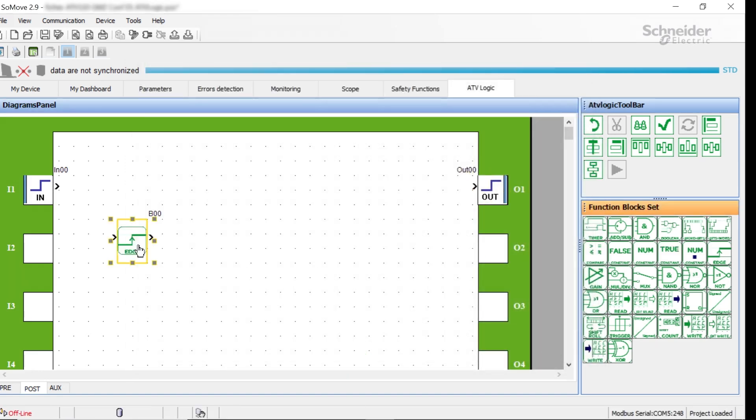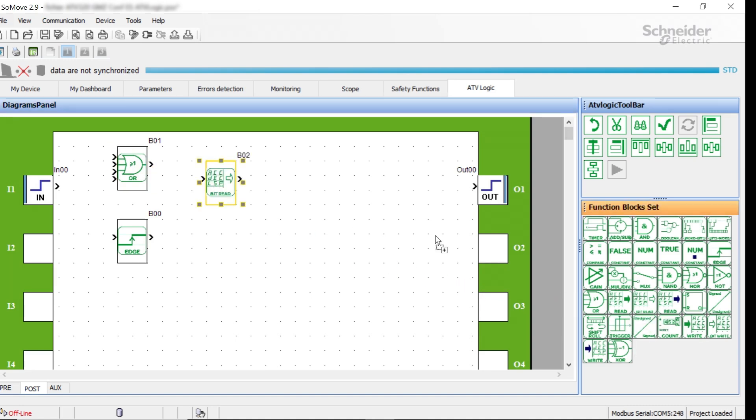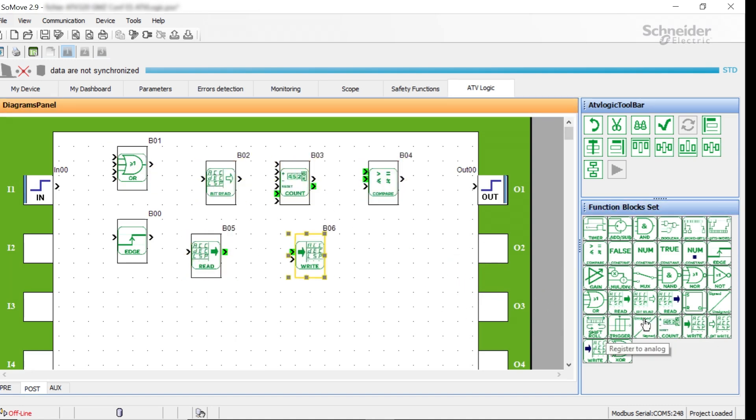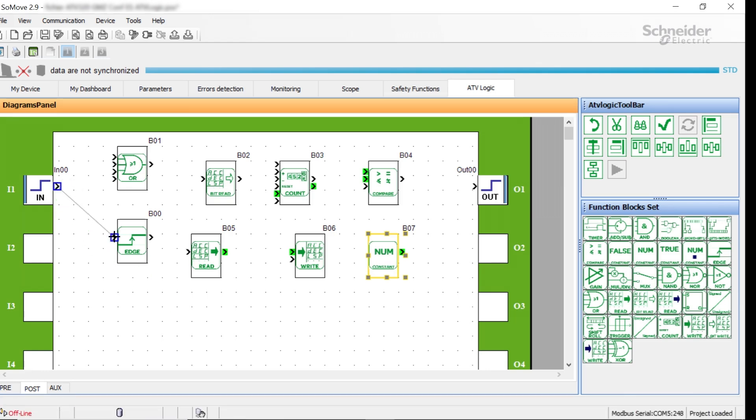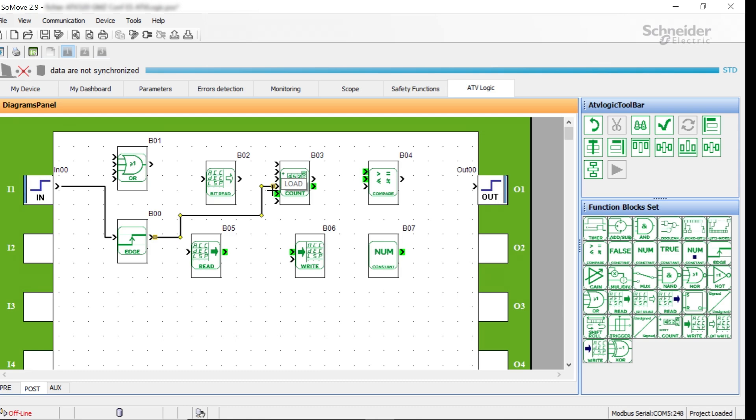Build the program. In the ATV logic toolbar, choose the desired block and drag and drop it onto the frame. Connect the inputs and outputs to the blocks. Connect logic signals to logic inputs of the blocks. The edge block avoids a disturbed signal on DI1. Connect the output of the edge block to the load input of the count block.